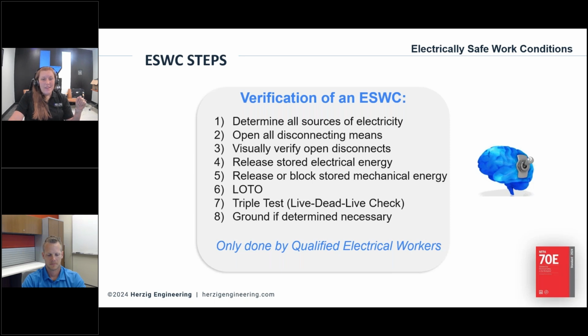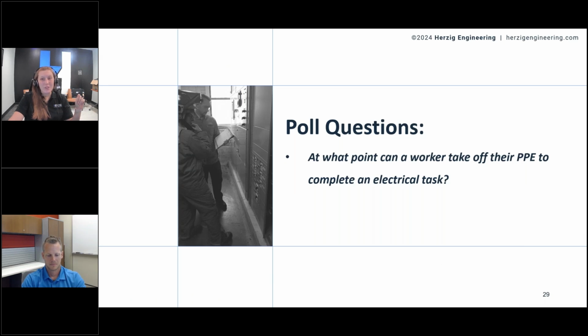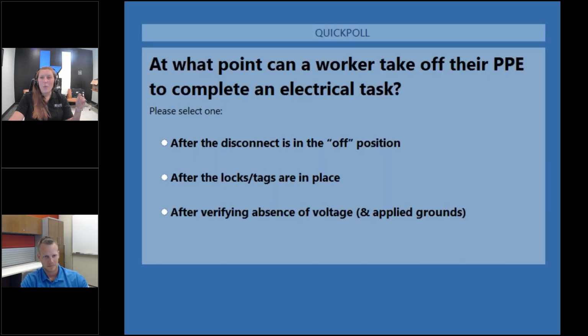And then, my next question here that came up, when do you need PPE on? Which is great because my next polling question actually was going to test to see if you guys could answer it. So at what point can a worker take off their PPE to complete an electrical task? After the disconnect's in the off position, after locks and tags are in place, or after verifying absence of voltage and applying temporary grounds if needed.